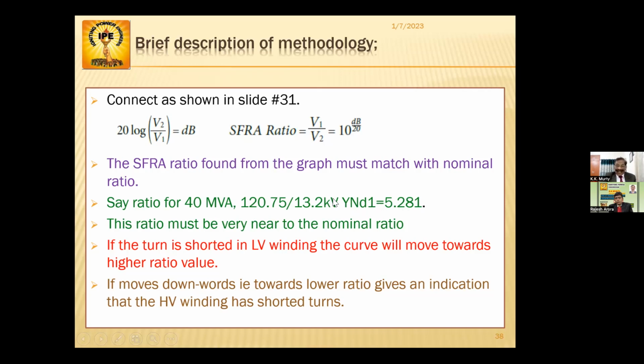So the ratio is 5.281. This is 120 divided by root 3, sorry, yeah, 120 divided by root 3 divided by 13.2 kV. That comes to 5.281. This ratio must be very near to the nominal ratio. If the turn is shorted in the LV winding, the curve will move towards a higher ratio. Why will it go towards a higher ratio?